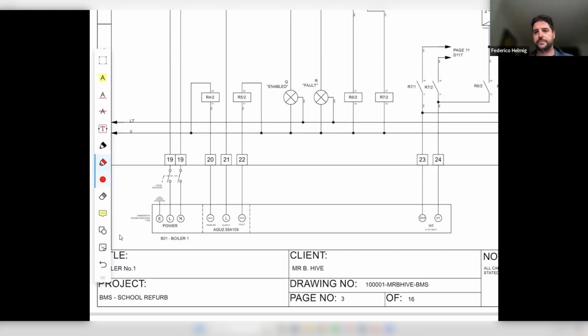If I remember off the top of my head, the spec does detail that it needs to be a 0 to 10 volt control signal. Even if it doesn't say that exactly, it does say we need to modulate the heat of the boiler - some sections say we need to bring the boilers up to temperature, then bring them back down and level them off. So the language used indicates it needs to be modulated, not just on or off.